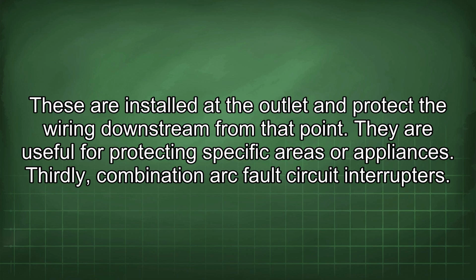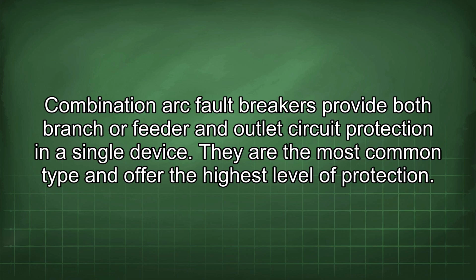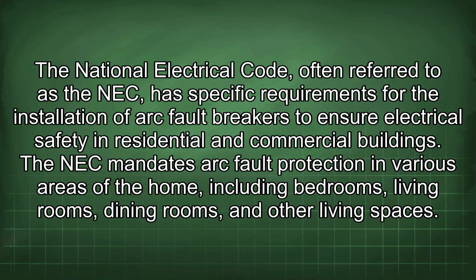Thirdly, combination arc fault circuit interrupters. Combination arc fault breakers provide both branch or feeder and outlet circuit protection in a single device. They are the most common type and offer the highest level of protection. The National Electrical Code, often referred to as the NEC, has specific requirements for the installation of arc fault breakers to ensure electrical safety in residential and commercial buildings.